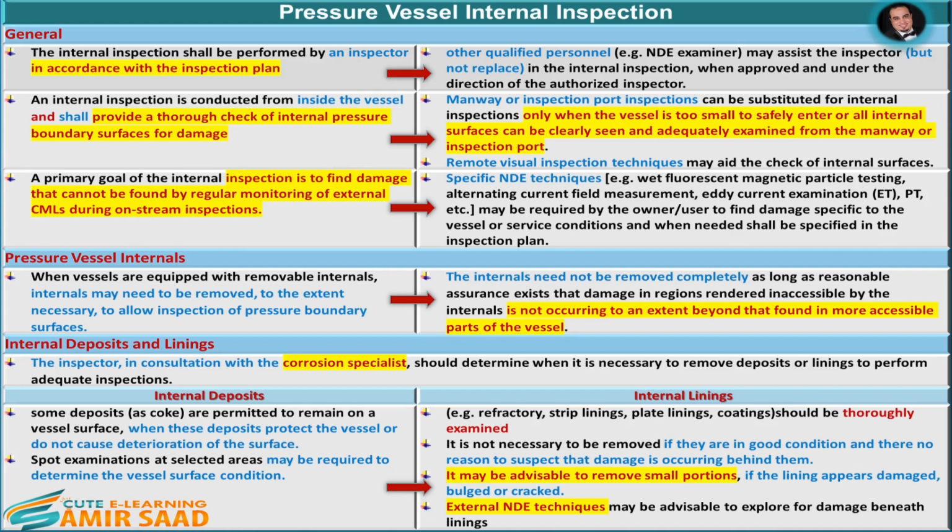Internal deposits. Some deposits, such as coke, are permitted to remain on a vessel surface when these deposits protect the vessel or do not cause deterioration of the surface. Spot examinations at selected areas may be required to determine the vessel surface condition.